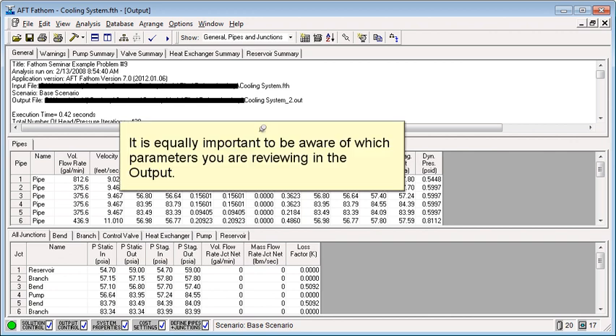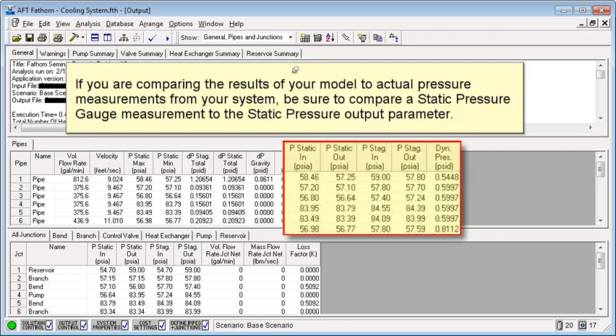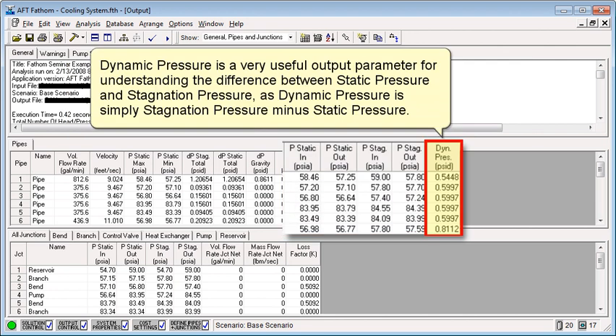It is equally important to be aware of which parameters you are reviewing in the output. If you are comparing the results of your model to actual pressure measurements from your system, be sure to compare a static pressure gauge measurement to a static pressure output parameter.